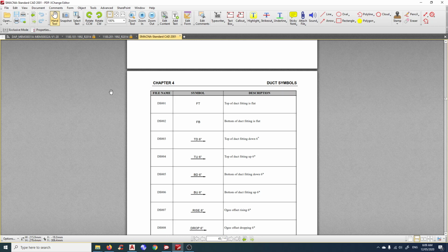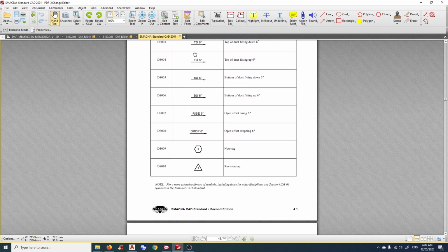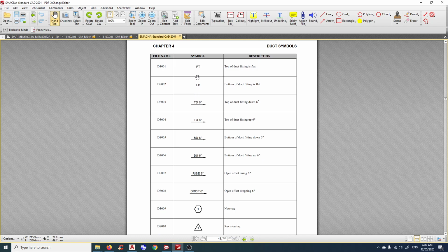Duct symbols. Of course it's in inches, but we normally follow the symbols quite faithfully in our industry. FT, top of duct fitting is flat. It means if you have a transition, the top of the fitting is flat, so the transition is either on the sides or on the bottom. We leave that decision to the duct manufacturer, but they want the top flat. The reason is you can mount that fitting as high as possible against, say, the slab above, or a roof above, very close.